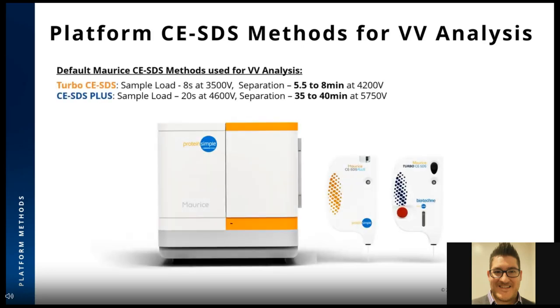While there are varied methods to prepare the viral vectors, the good news is that the Maurice CESDS methods are platform. We use the default Maurice CESDS methods for all of our viral vector analysis. Shown here are both the Turbo CESDS and CESDS Plus cartridge conditions and run conditions, including injection times and voltages and separation times and voltages. Now let's start taking a look at the individual viruses and some Maurice data to help support CQA analysis.